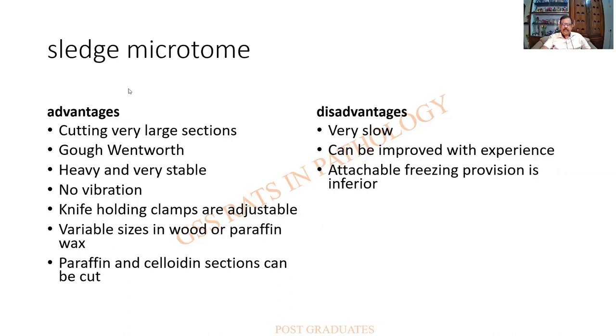Advantages of the sledge microtome: very large sections can be cut — it was first used by Gough and Wentworth in demonstrating emphysema specimens of the entire lung. It is heavy, very stable, with no vibrations. Knife-holding clamps are adjustable, and varying sizes can be cut in wood or paraffin wax. Both paraffin and celloidin embedded sections can be used.